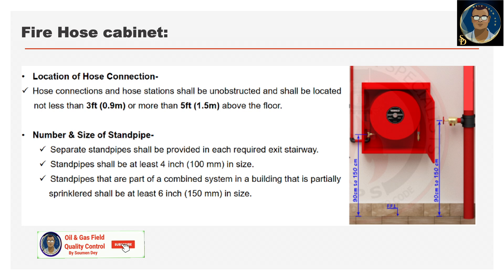Regarding number and sizes of standpipes: separate standpipes shall be provided in each required exit stairway. Standpipes shall be at least 4 inches in size. Standpipes that are part of a combined system in a building that is partially sprinklered shall be at least 6 inches or 150 mm in size.